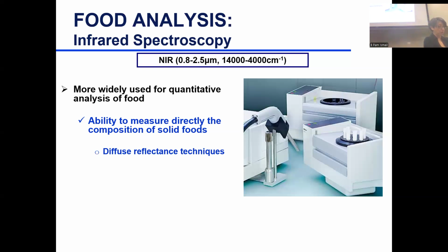It gives you a whole spectra, and then there are regions: this is the region for protein, this is the region for lipid, this is the region for water. So it gives you regions that, as an analyst, you can select and then quantitate. The Fourier transform calculator, it happens very quickly. It just gives you a number. You can choose to see the spectra, or it just gives you the percentage. It's calibrated, it just gives you the percentage.